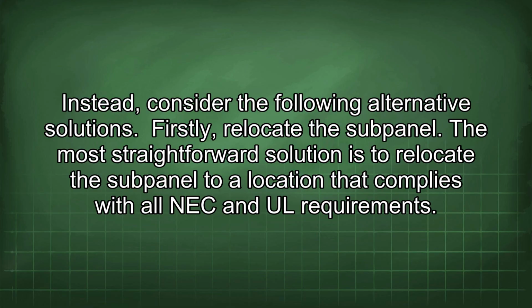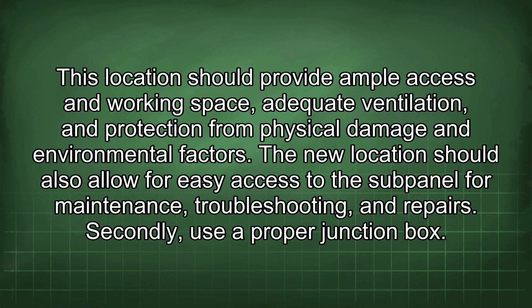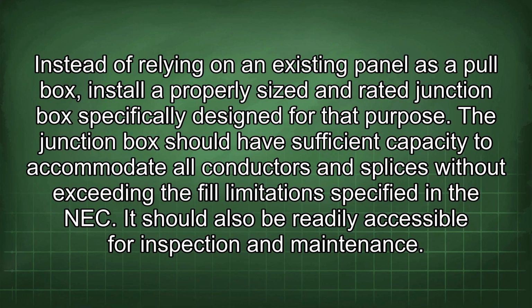Firstly, relocate the subpanel. The most straightforward solution is to relocate the subpanel to a location that complies with all NEC and UL requirements. This location should provide ample access and working space, adequate ventilation, and protection from physical damage and environmental factors. The new location should also allow for easy access to the subpanel for maintenance, troubleshooting, and repairs. Secondly, use a proper junction box. Instead of relying on an existing panel as a pull box, install a properly sized and rated junction box specifically designed for that purpose. The junction box should have sufficient capacity to accommodate all conductors and splices without exceeding the fill limitations specified in the NEC. It should also be readily accessible for inspection and maintenance.